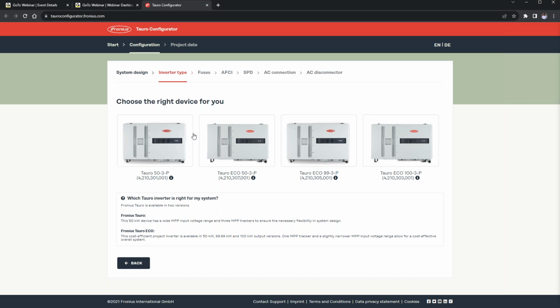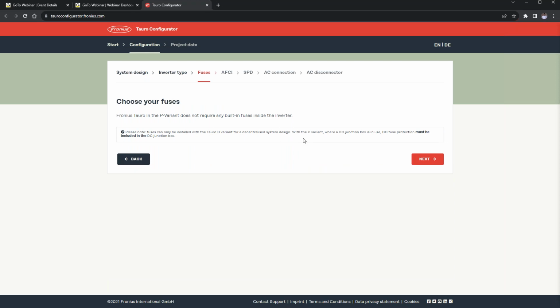Next up is to select the inverter type. So you now select the inverter you want to make use of. So let's say we go for the Tauro Eco 100. And then, yeah, we can now see while trying to select fuses, it tells us that the Fronius Tauro in the P variant does not require any built-in fuses inside the inverter. This is basically because we're making use of DC combiner boxes. So in this case, the DC fuse protection must be implemented inside the DC combiner boxes.